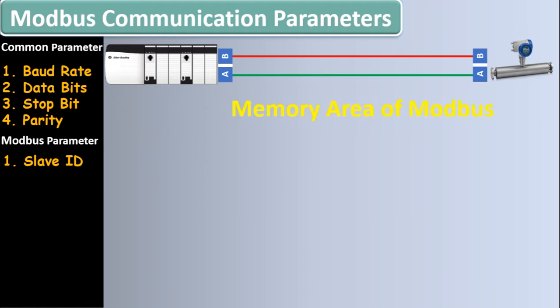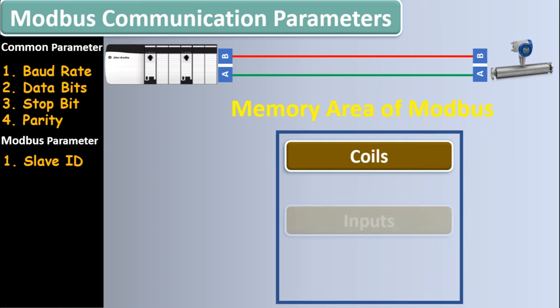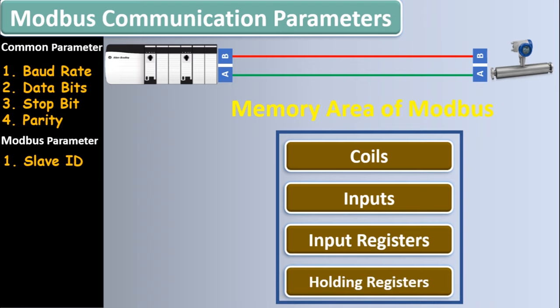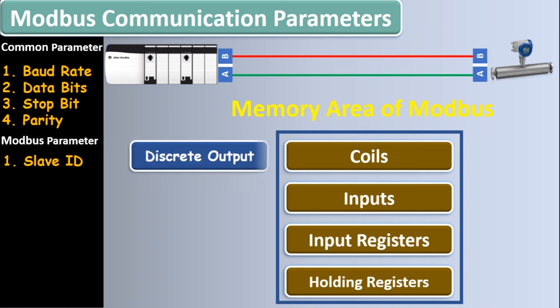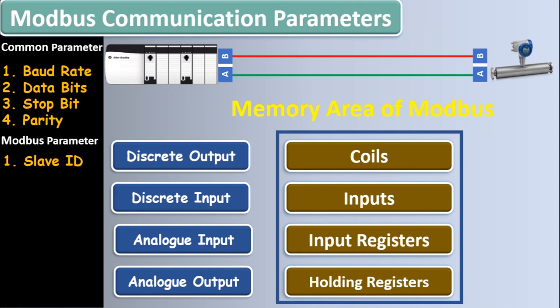Starting with the memory area of Modbus: it consists of four parts — coil, input, input register, and holding register. Modbus was introduced by Modicon and its memory area was defined just like the memory area of a PLC. Coil corresponds to discrete output in PLC; input corresponds to discrete input in PLC; input register and holding register correspond to analog input and analog output in the PLC. Coils and inputs have one bit of data, while input registers and holding registers are 16 bits of data.